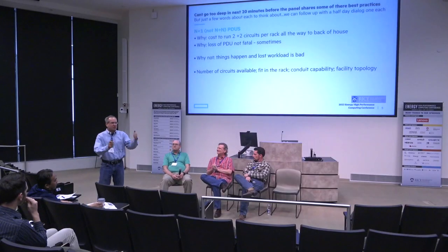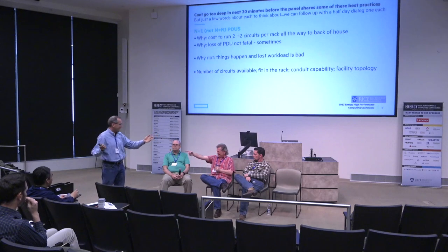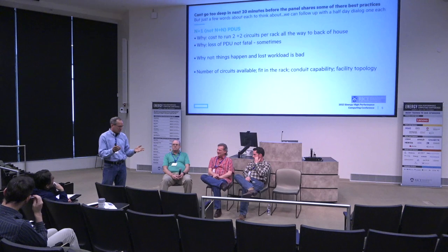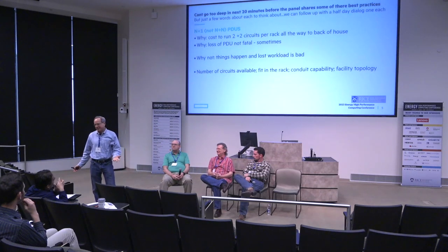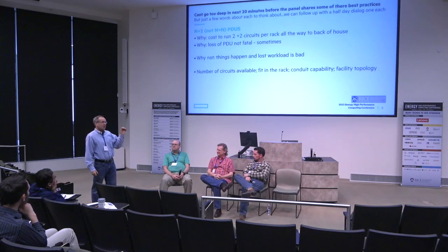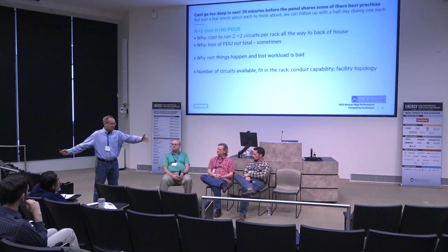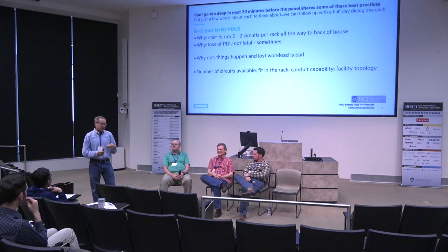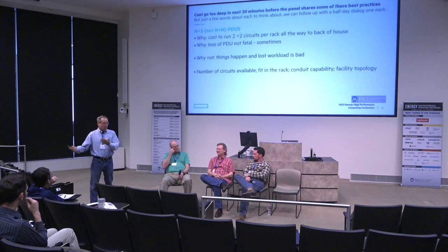Well, not in that part of the data center, because it was very costly. All of those things used to be part of the double conversion UPS that we had. Exactly, and now that went away, because now it's not double conversion. They used to be inside the bulk power factor correction of the power supplies, and everybody says no, we need to take that out. Well, guess what happens then? A lot of facilities used to have large enough air handlers and other larger AC moving equipment that one AC device could make up for a lot of harmonics. But now it's all coming from raw DC.